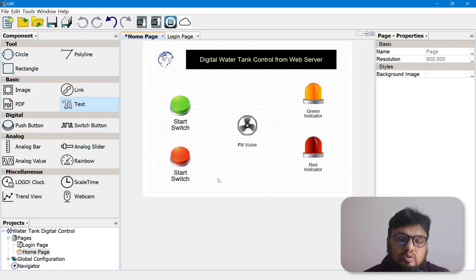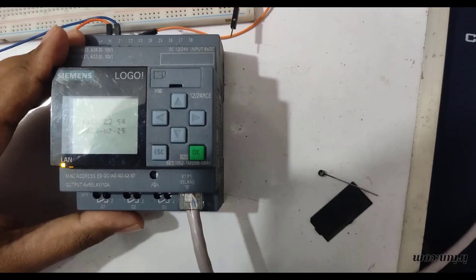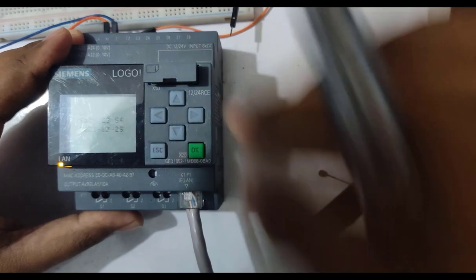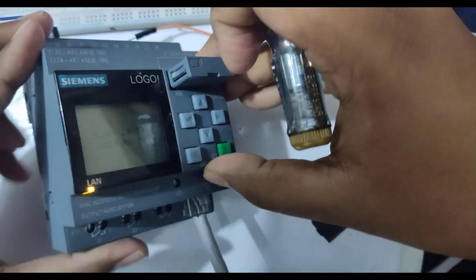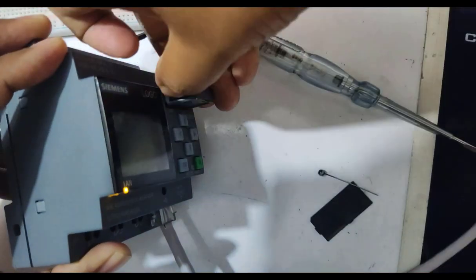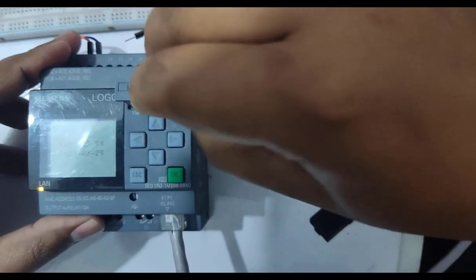Remember that when uploading this program to the LOGO PLC, you must have an SD card installed, because without an SD card it will not work. On the right top corner there is an SD card slot on your LOGO PLC. Open this slot and you will find a dedicated slot for SD card insertion — you can insert your standard SD card memory to hold the web server program as well as your PLC program.